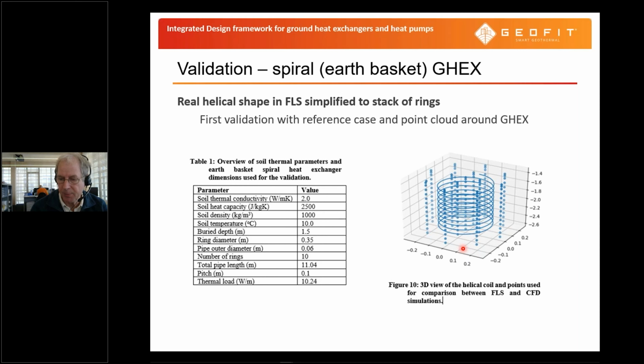Now, an additional problem is that because the geometry is slightly different, we cannot compare directly between the analytical solution and the CFD solution, because the position of the ring is slightly different, and you can also imagine that the inclination of the ring makes a difference. So what we did is define a point cloud, at small distances and slightly larger distances, around the earth basket type heat exchanger, and then compare the CFD solution and the analytical solution for that point cloud, because then we get a better match between the geometries. Again, the different parameters were equal between the CFD and the earth basket type heat exchanger.